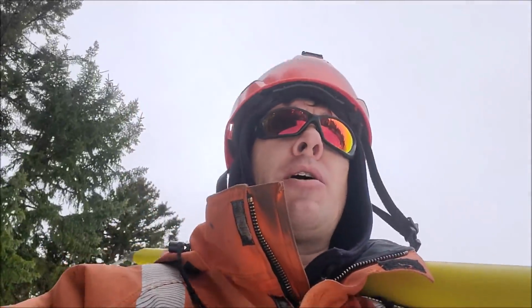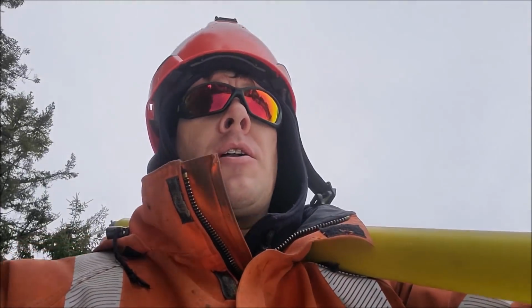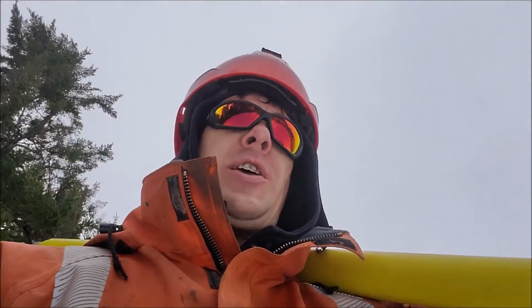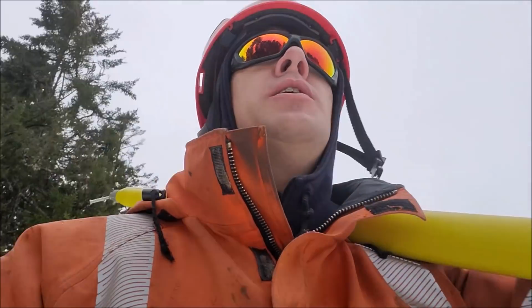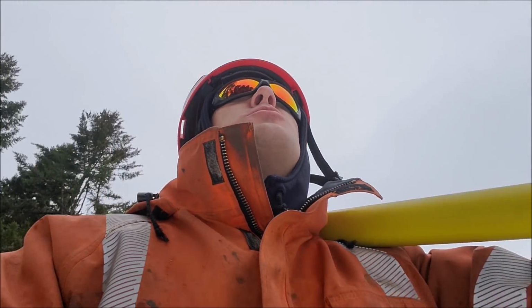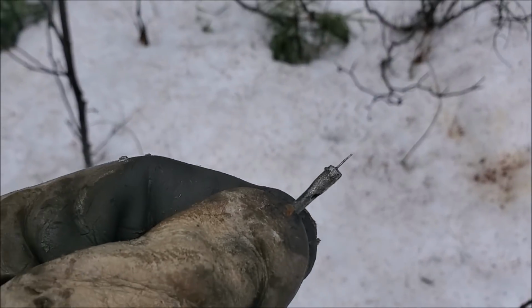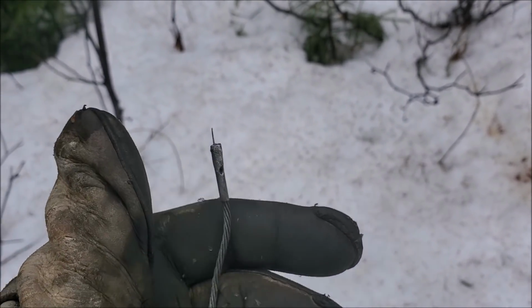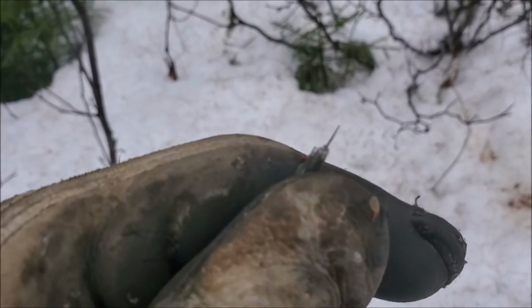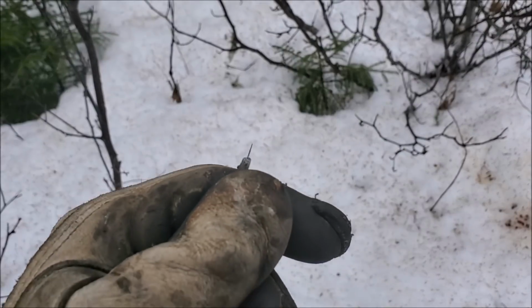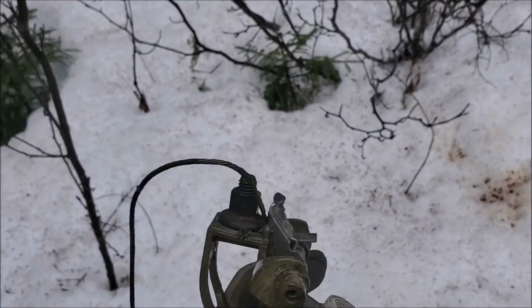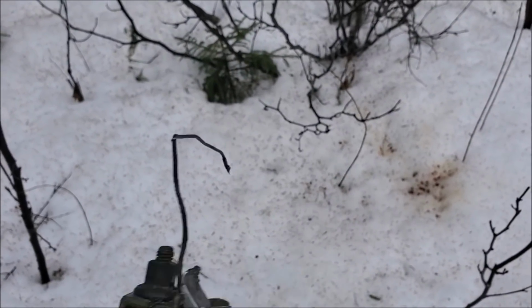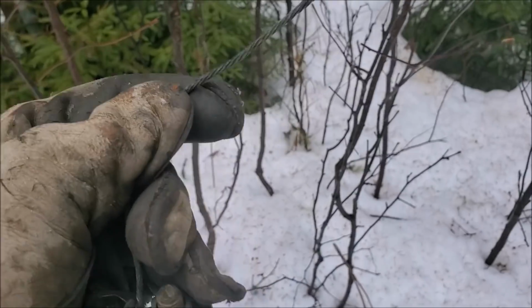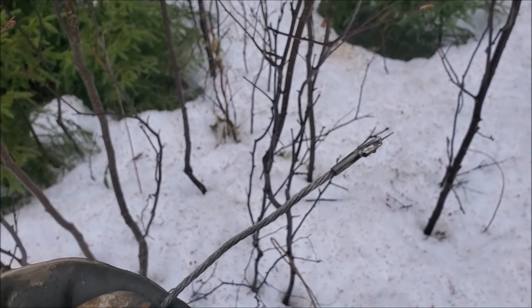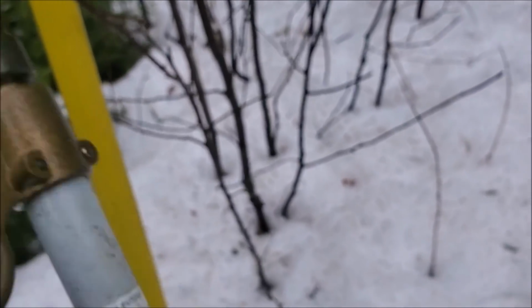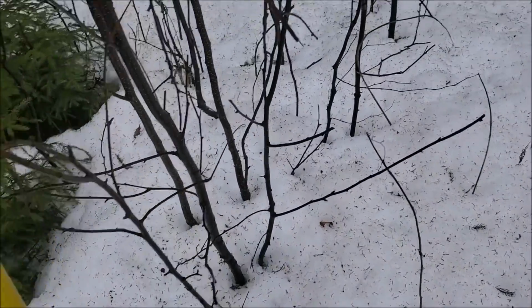There's three-phase power going all through the park. It's all underground lines. The feed for the underground, there's one phase blown, center phase blown. It looks like it could just be fuse fatigue. The actual fuse link, you can see here, it's simply melted off that little tiny piece in the end. A lot of times if you come across a door that's open and the fuse looks like that, it's simply melted off from overload or fuse stress. Fuse fatigue, we call it. It could also be a fault. It could still be a fault.